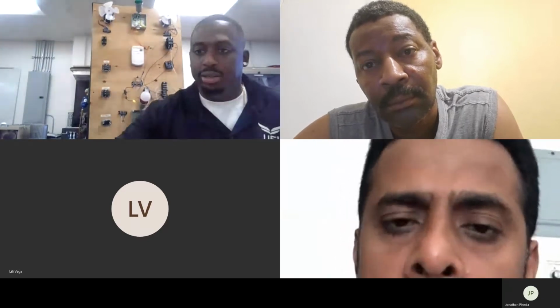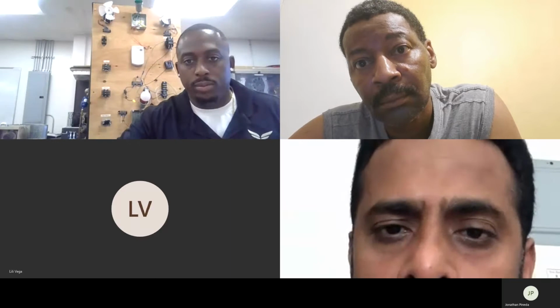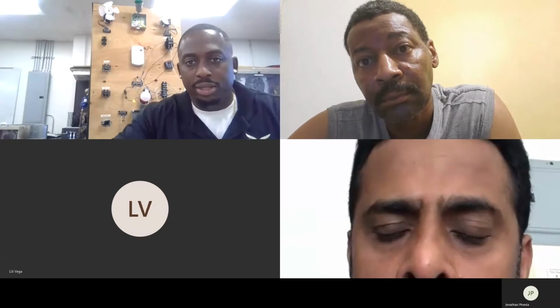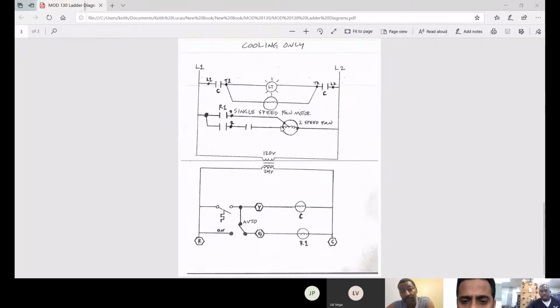So our coil is connected. Now let's go back to our contactor. So we got our L1 connected, our L2, we have our coil connected between common, which is here, that's C here - this is our whole common side - and then we have our Y here. So our coil is connected properly.